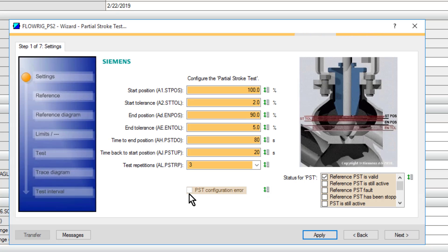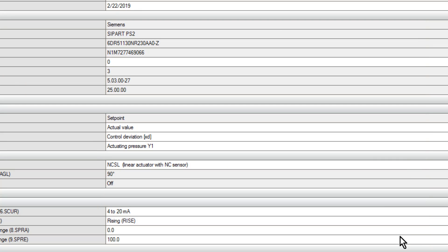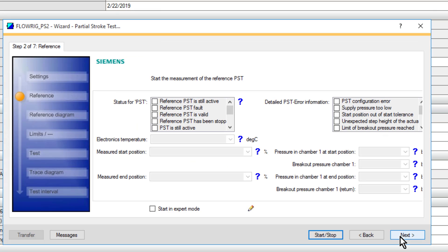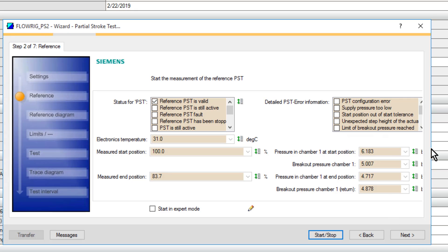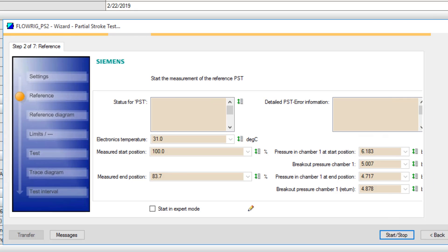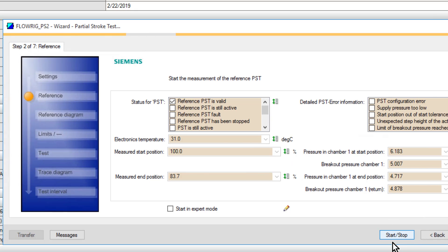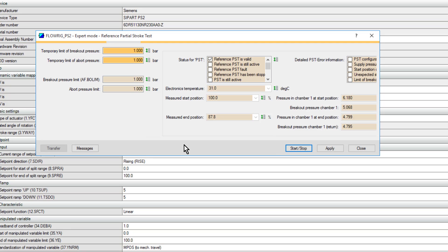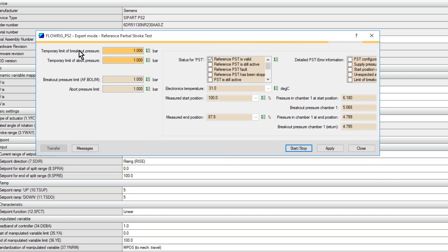We'll go on to next, and here we can carry out a partial stroke test. But what I'm going to do is just tick on this expert mode so we can have a look at what's actually going on in the background. Here we have the expert mode for the partial stroke test, and I can see on here my breakout pressures before and after.